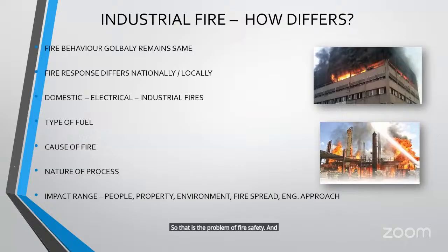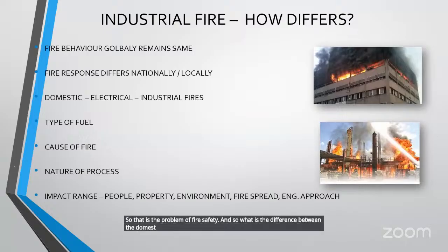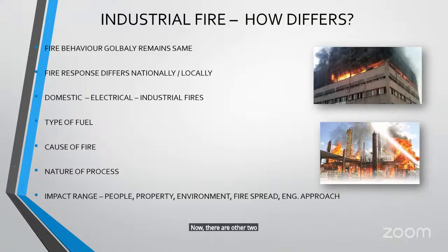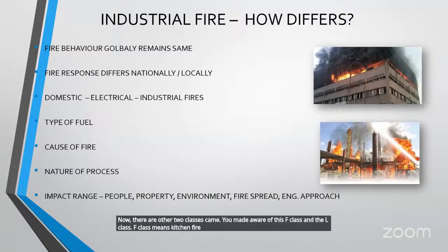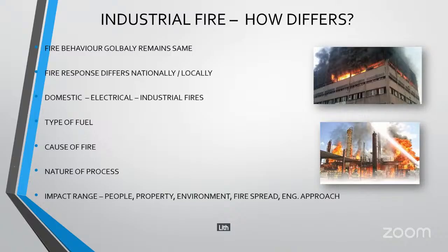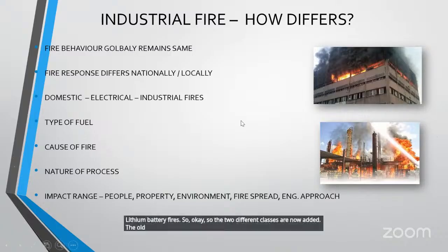And so, what is the difference between domestic, electrical, and industrial fires? The difference of the industrial fire depends upon the factors mentioned below, the type of fuel. So, the A class, B class, C class, D class, you know. Now there are two other classes that came. You might be aware of this, F class and L class. F class means kitchen fire. L class means lithium battery fires. So the two different classes are now added. The old classification is A, B, C, D. D may not be there in the homes, but on the industrial side it may be there.